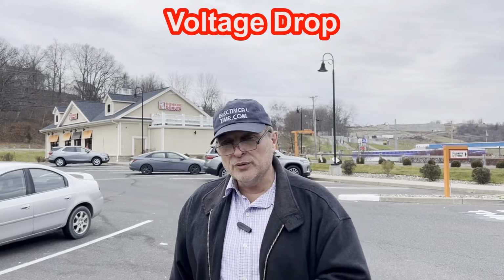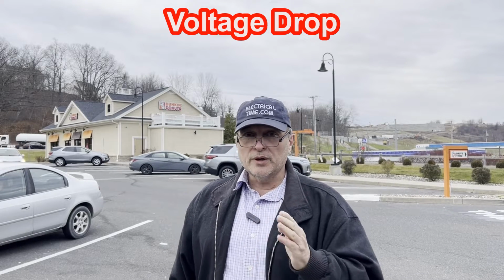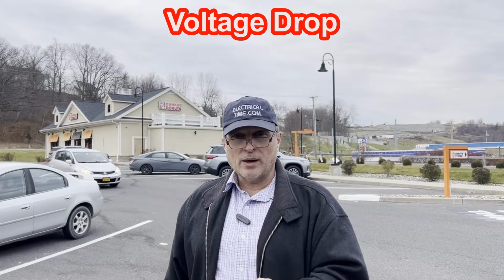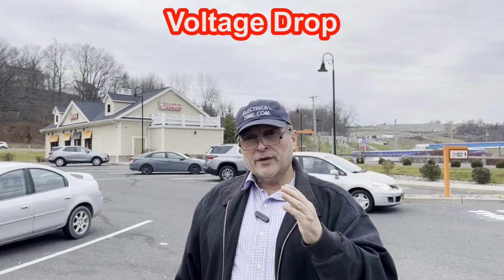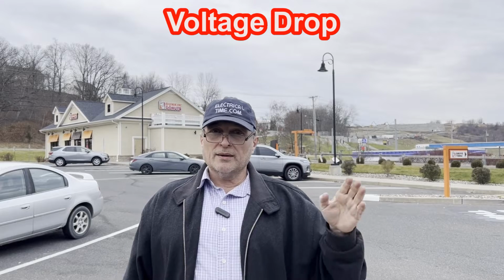And why is that? Because we have to account for voltage drop. It's a real problem that's out there. Because if we've got a long run and those lights are not getting the proper voltage, they're probably not going to work properly. All right, so let's say we have a total distance one way of 500 feet.